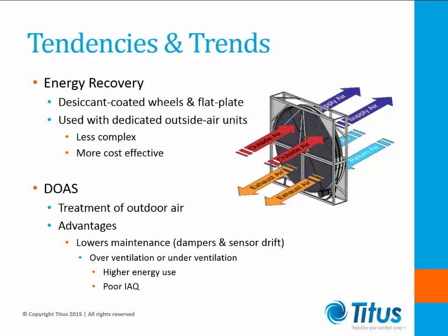Which brings up the important second feature of this slide. For many climates, the toughest part of an air handling unit's job is treating outdoor air. Coils must be sized to handle the most extreme ambient temperatures. In humid climates, dehumidification requires air to be cooled below the mixed air's dew point, even if the occupancy of the building might not require such a low temperature. Additionally, mixing dampers and their associated control sequences in air handling units are common modes of failure, which together with sensor drift can result in overventilation, known as higher energy use, or underventilation, known as poor indoor air quality.